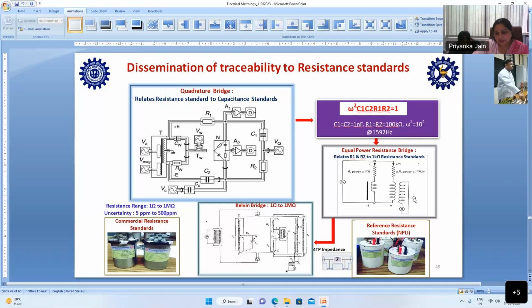So this is the special arrangement and excitation current setup which we maintain here at NPL. Then we have these resistance standards derived from the Kelvin bridge, and these are the commercial resistance standards which come to us for calibration, and the uncertainty range for the customers is 5 ppm to 500 ppm.